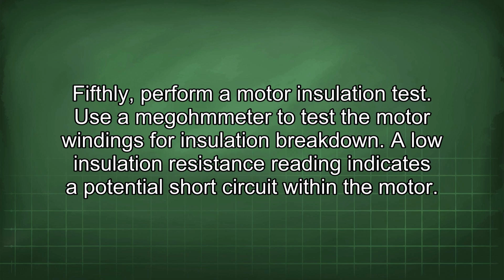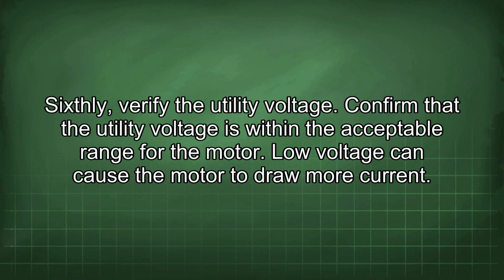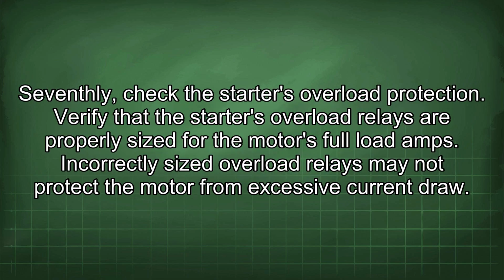Fifthly, perform a motor insulation test. Use a megohmmeter to test the motor windings for insulation breakdown. A low insulation resistance reading indicates a potential short circuit within the motor. Sixthly, verify the utility voltage. Confirm that the utility voltage is within the acceptable range for the motor. Low voltage can cause the motor to draw more current. Seventhly, check the starter's overload protection. Verify that the starter's overload relays are properly sized for the motor's full load amps. Incorrectly sized overload relays may not protect the motor from excessive current draw.